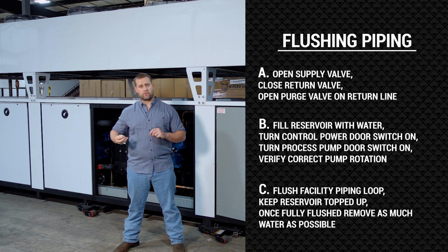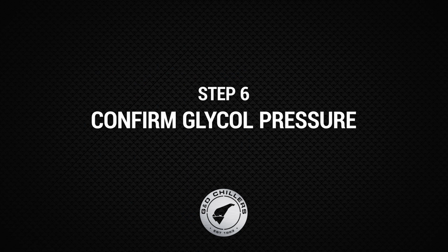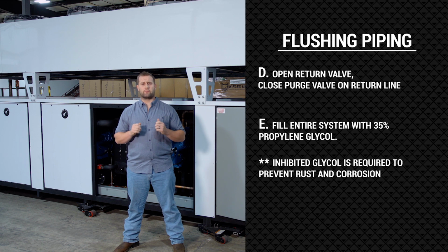After it is clean and clear, you can button everything up, shut your pump off, open up your valves, and then start filling with propylene glycol. When you fill with propylene glycol, the key is to get inhibited propylene glycol. You want the inhibitors so there's no corrosion or any kind of organic growth. It'll keep your glycol and your piping in good shape, so that's a must. Once you add the propylene glycol, circulate it for about half an hour, then recheck with a refractometer that we provide for you and make sure it's at 35%. It needs to be at 35%. If you have any questions about glycol, feel free to call.